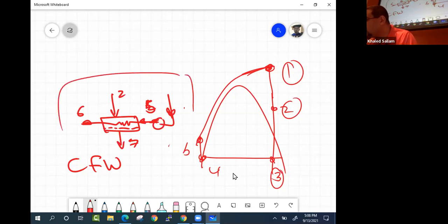So now to help the boiler a little bit, we use the closed feed water heater. It says 5 is so cold, let me heat it a little bit, so it heats it to 6. How does it do this? By using steam from here, from 2. And as the steam cools down and heats the water, it goes from 2 to 7.